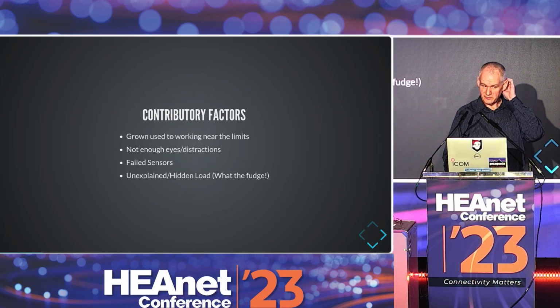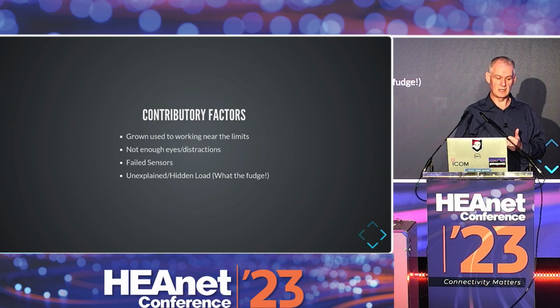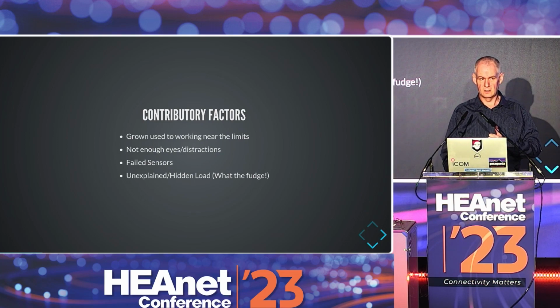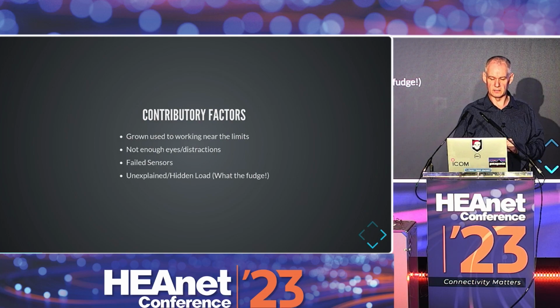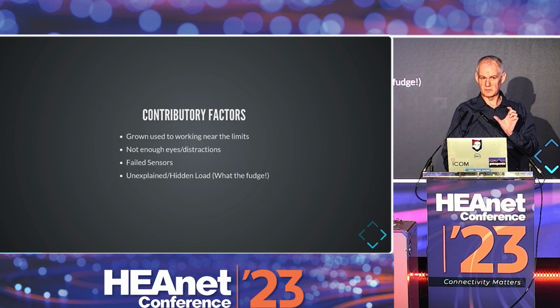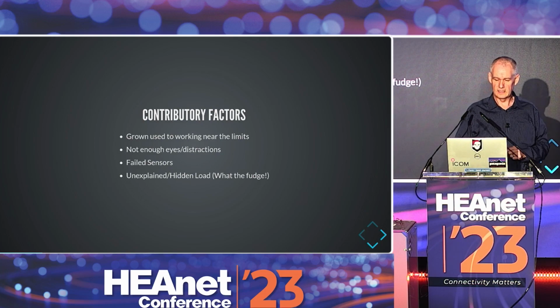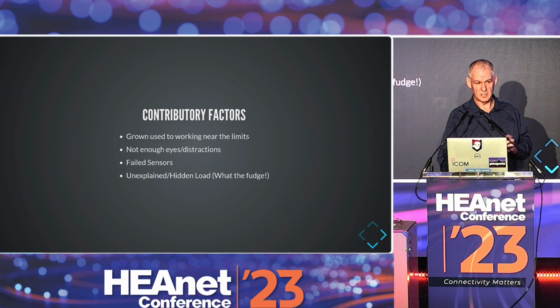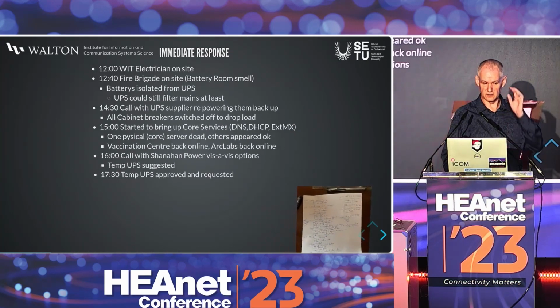So, contributing factors: we'd grown used to working near the limits of the system. Too many distractions in the office at the time. There were actually failed sensors we didn't know about, and there was unexplained load, which we figured out afterwards where it came from, that we weren't metering and didn't know about. So approximately 40 amps a phase, or about 40 amps of load, isn't metered in the building, which we found subsequently, which was actually just enough to shove us over the threshold. It's actually due to the heating systems in the building that generates that load.